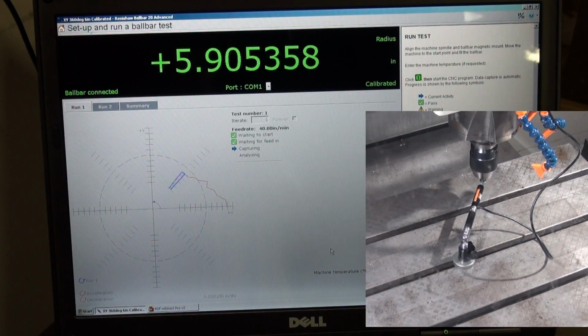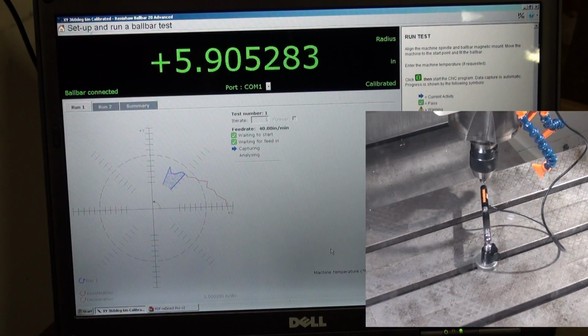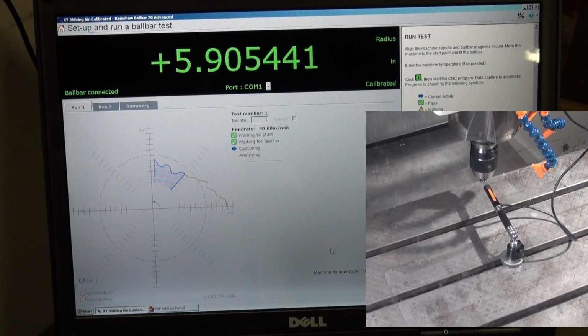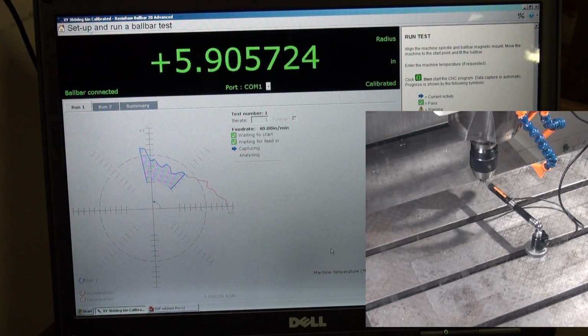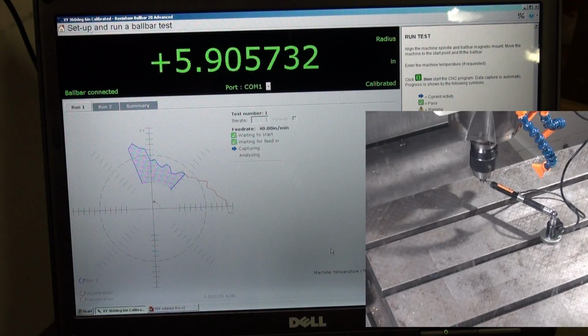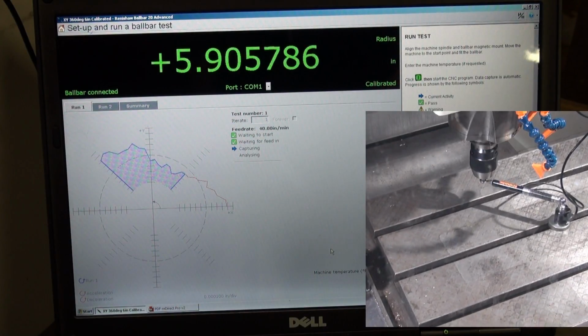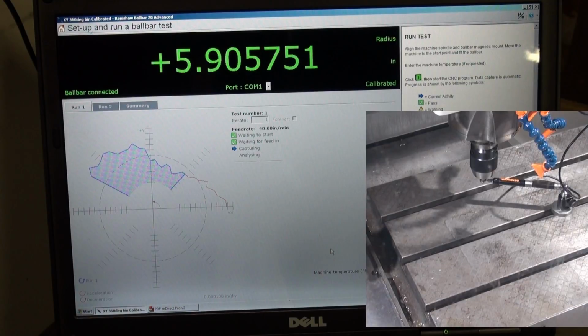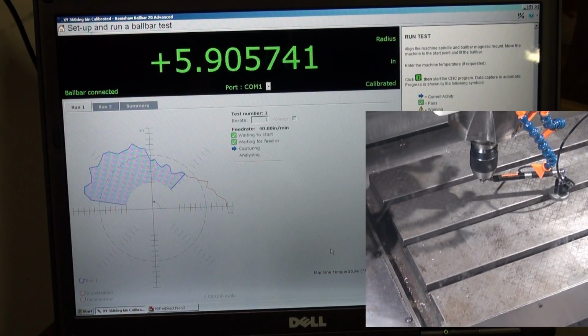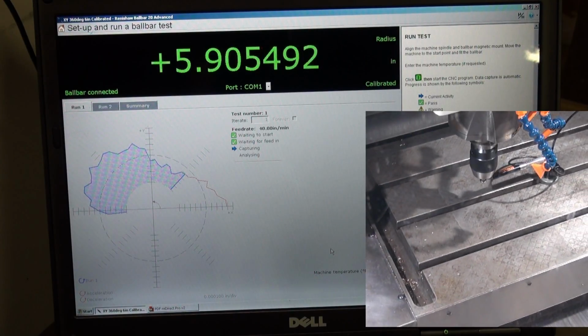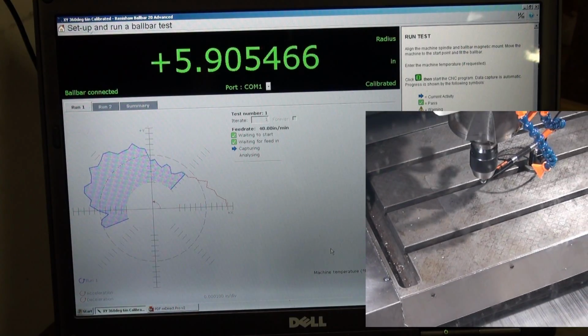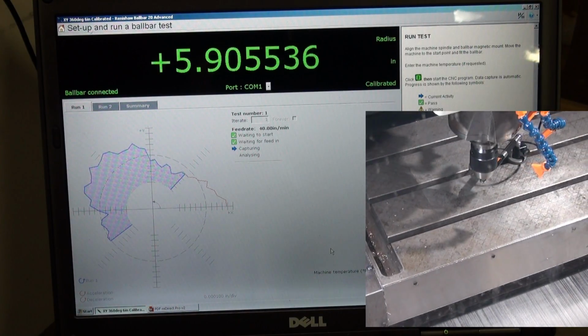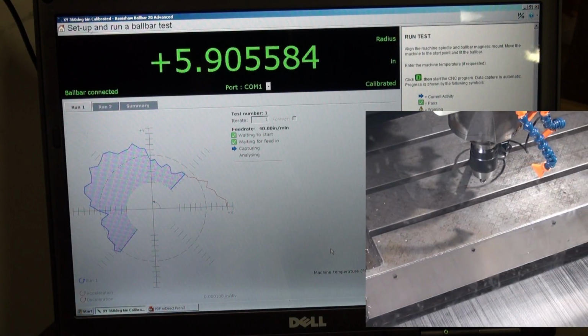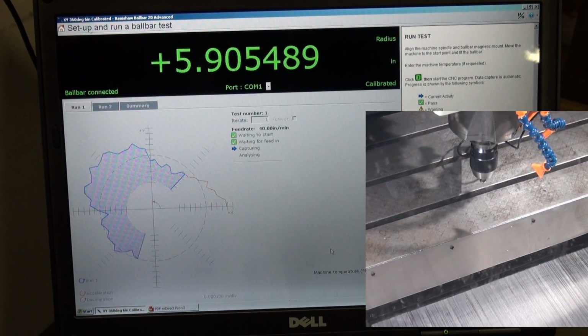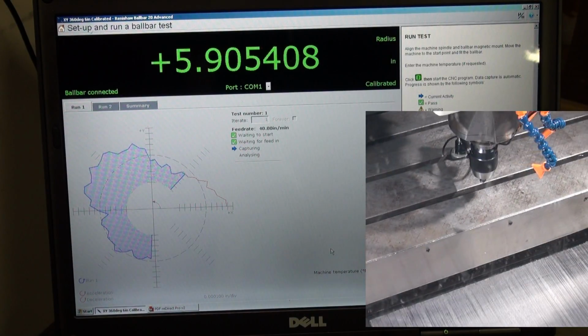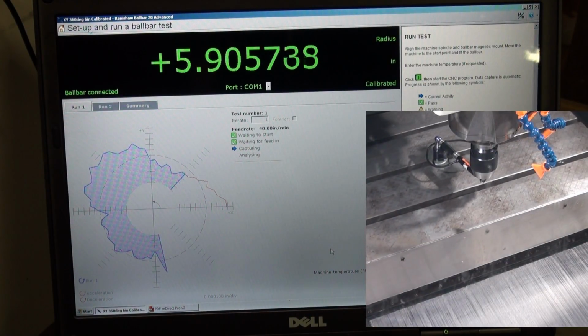Now this plot is an error plot. So the dotted line, the circular dotted line, is perfect. If you're over the dotted line on the outside of it, you're too big. If you're inside the dotted line, you're too small. Now Brian says that if the plot looks really bad, it actually means your machine's really good, because this plot auto scales. And right now the scale of each one of those little hash marks is 1/10,000th of an inch. So we're actually pretty good here.